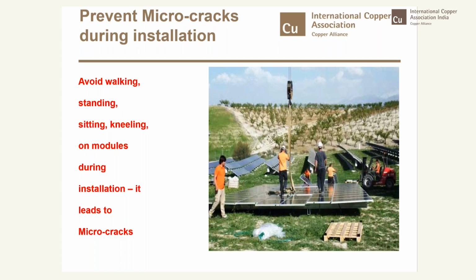So the contractor may install it, test it, hand it over and walk away. The crisis begins only after a year or so. The micro cracks slowly develop into hot spots, and the panel can ultimately be damaged. So this is a very crucial step, and very close supervision is required during installation. This does not happen much for ground systems, but for rooftops there is always a tendency for workers to cross over by standing or stepping onto the module. Let's see through a video.